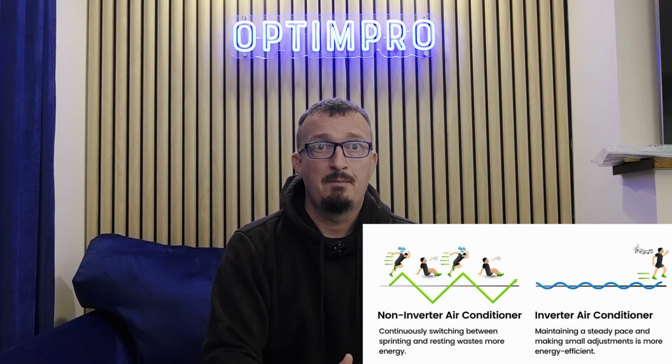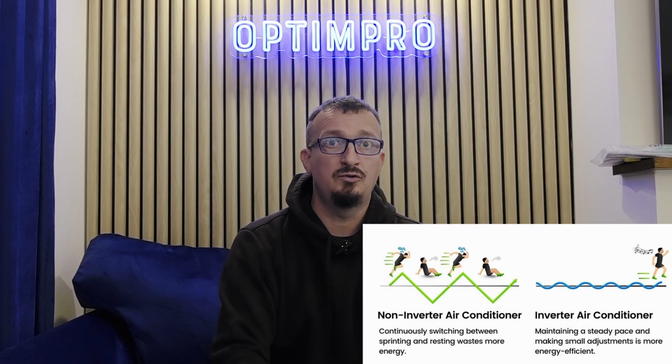Nowadays, almost all AC systems are the inverter type. What that means, without getting too deep into details, is that the compressor can be better controlled and its speed can be changed instead of having either on or off as options. Also today, all ACs are able to reverse the cycle and transform the condenser into an evaporator and the evaporator into a condenser. Basically, the outdoor unit will cool and the indoor unit will produce heat. The efficiency of this mode is very similar to the efficiency of the cooling mode.